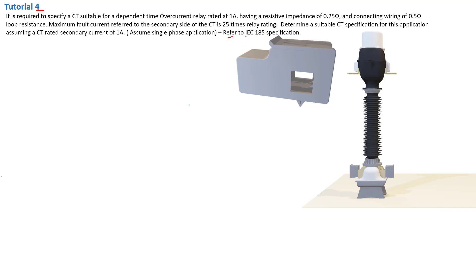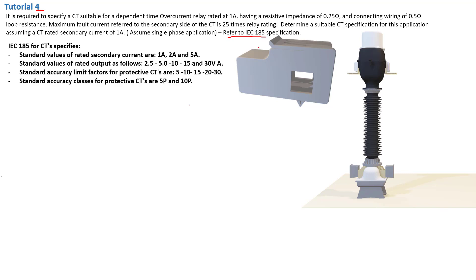We need to solve this circuit according to the IEC 185 specification. The IEC 185 specification states that standard values of rated secondary current are either 1 amp, 2 amps, or 5 amps — nothing in between. That's how manufacturers design these current transformers. We also have standard values of rated output, which is the CT burden in volt-ampere, ranging from 2.5 up to 30 VA.